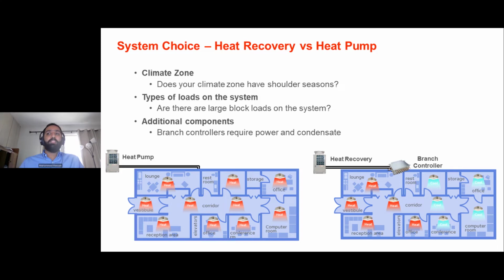So what drives the choice between heat pump and heat recovery? It comes down to a few large considerations, right? So does your climate zone have shoulder seasons? If you're in Arizona or Florida, where cooling is going to be a large percentage of your load for a significant portion of the year, then simultaneous heating and cooling is probably not needed. And it also might come down to the space that you're working with. Is it a gym area in a K through 12 school, or is it an admin area with some interior zones and some exterior zones, which might experience different thermal conditions in those shoulder seasons?